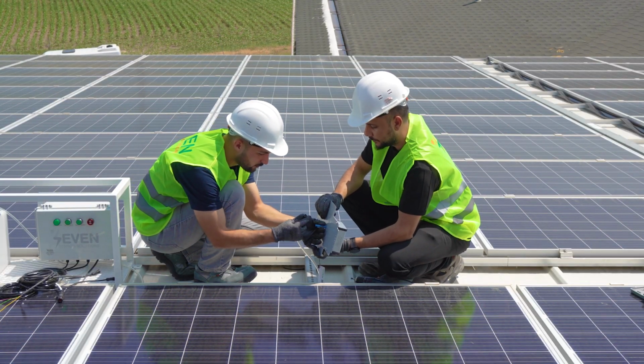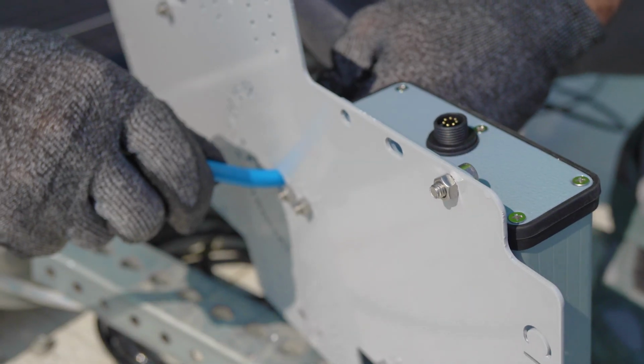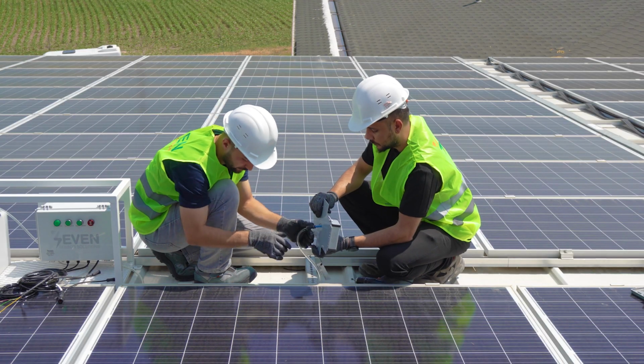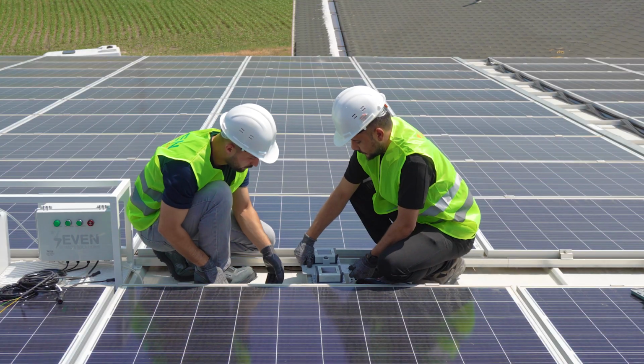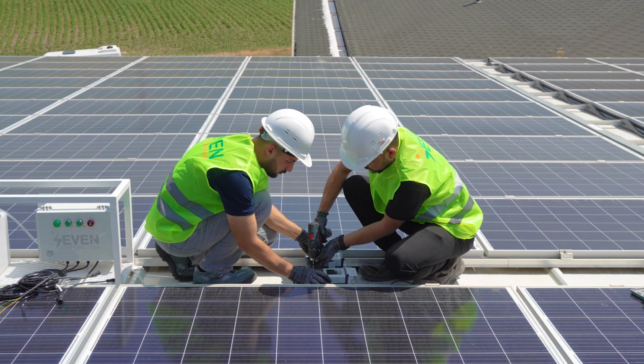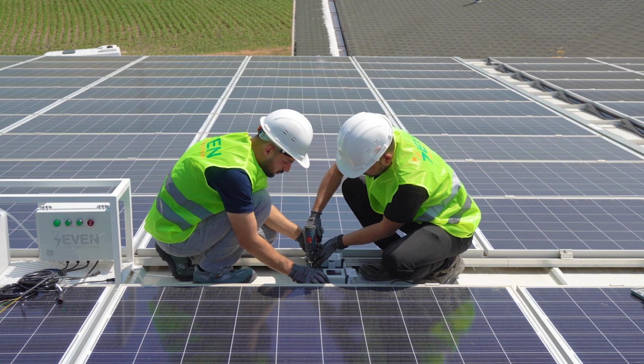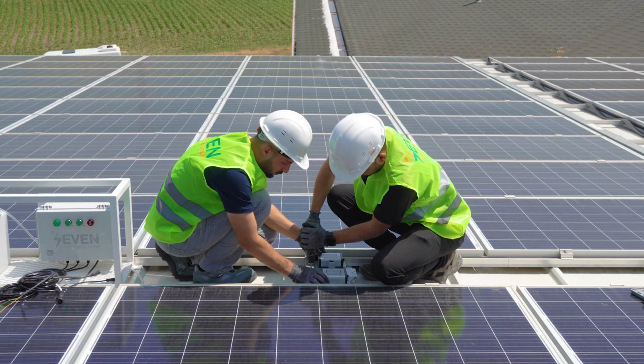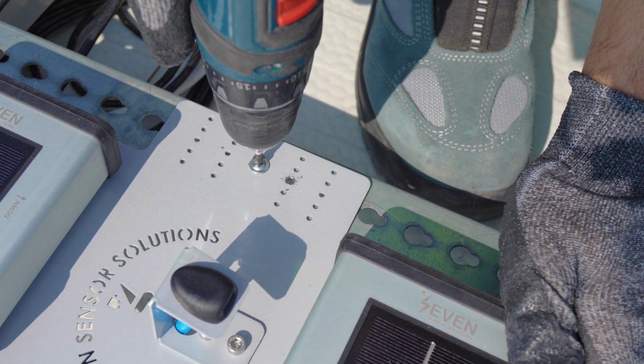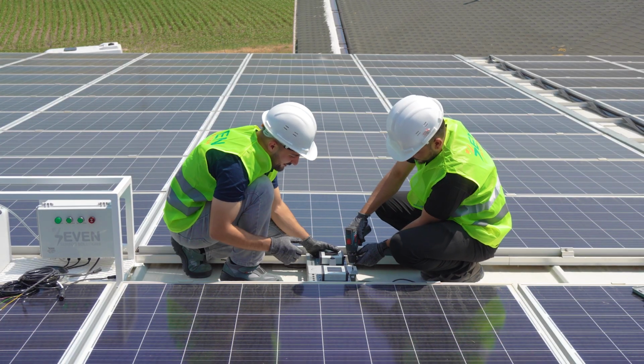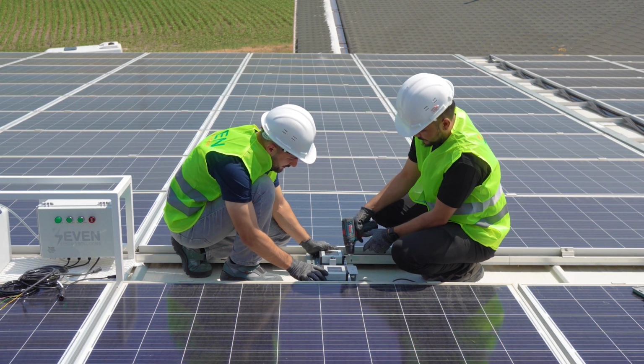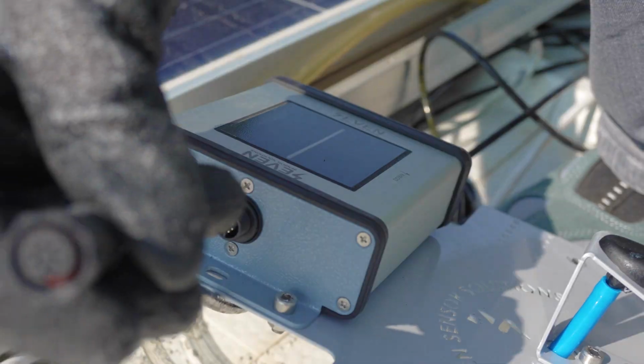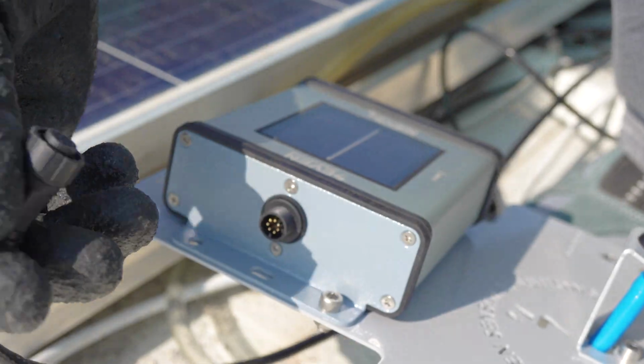Now, connect the pump hose to the nozzle hose behind the reference cells. Install the reference cell bracket so the cleaned sensor is on the bottom. On tracking systems, make sure this orientation is maintained during cleaning time. Mount the sensors at the same tilt and azimuth as the solar panels.